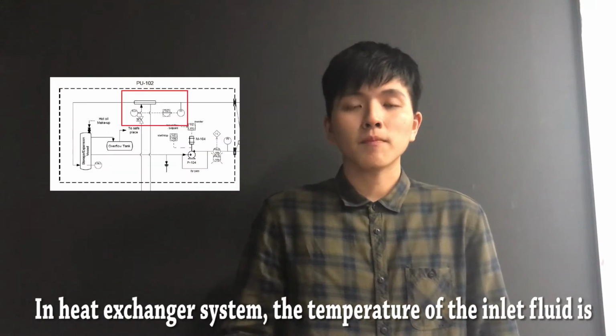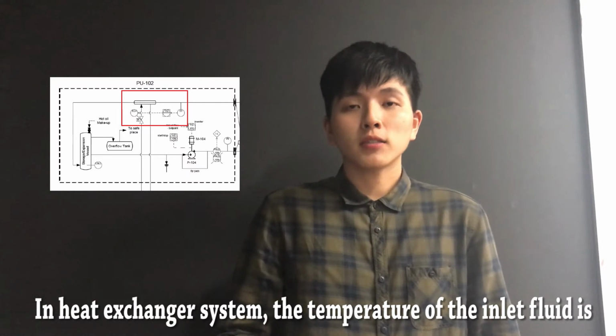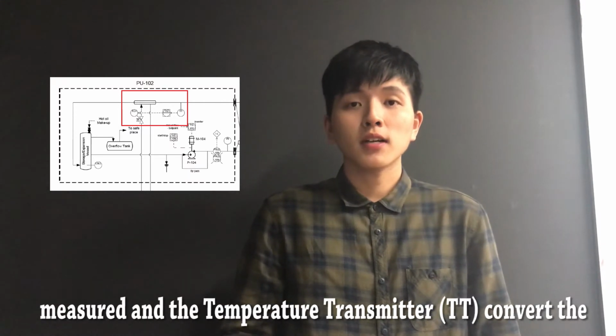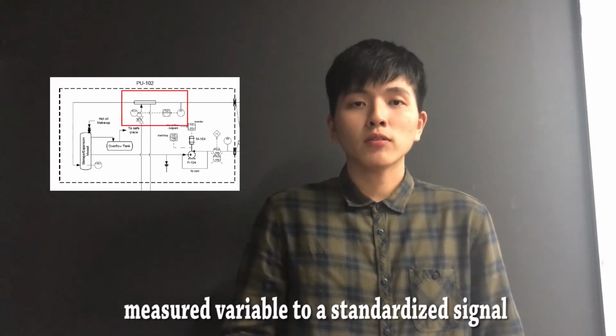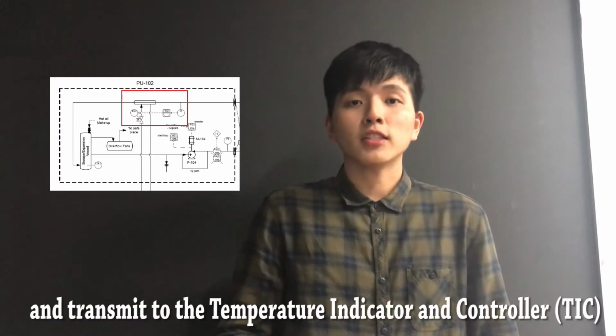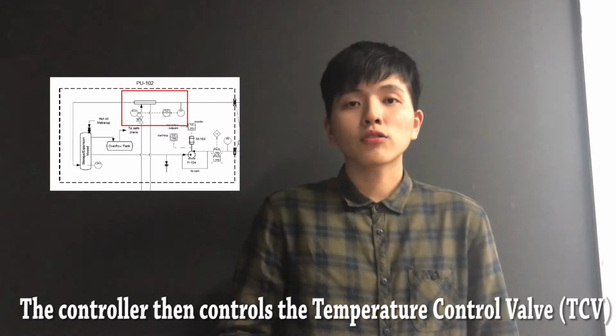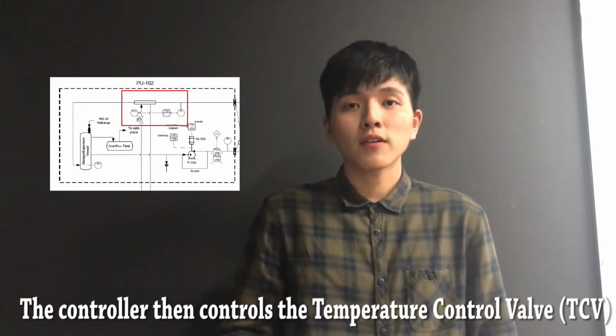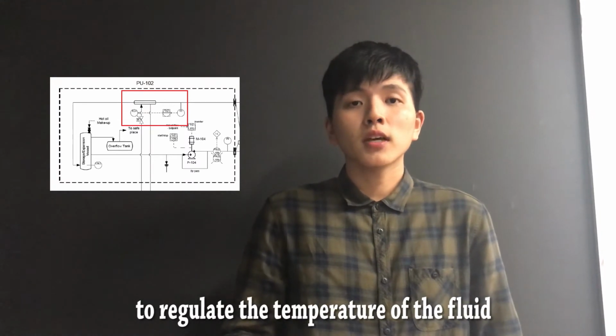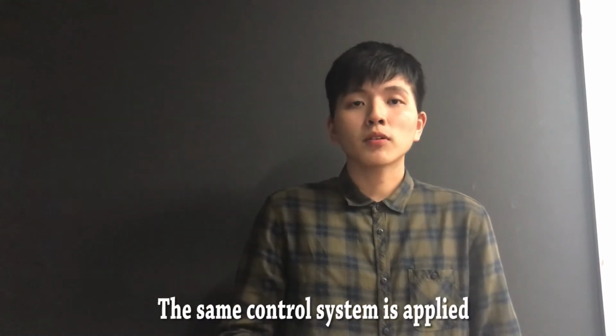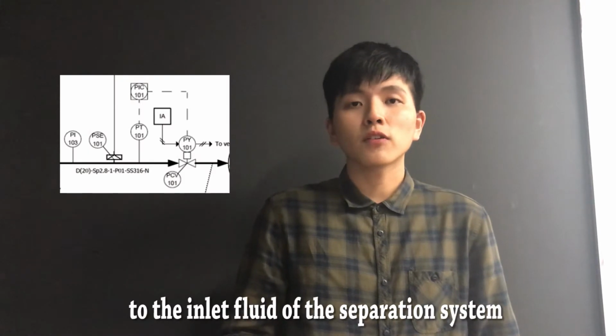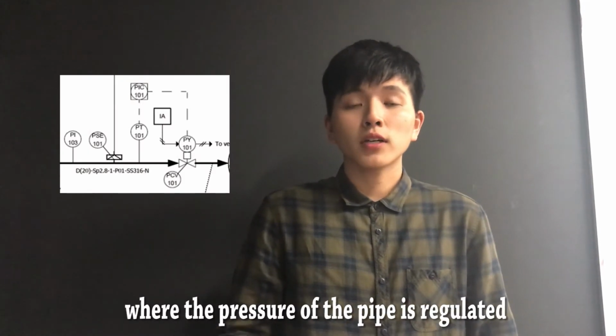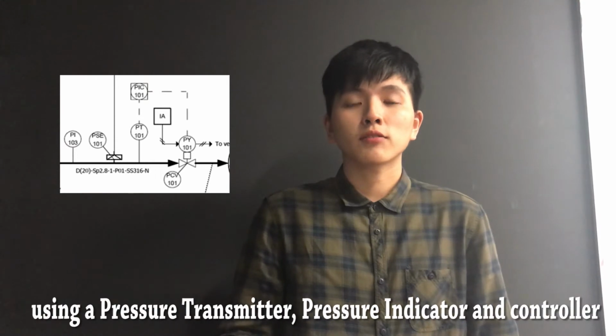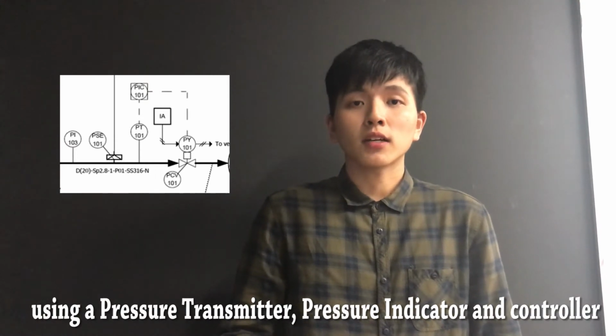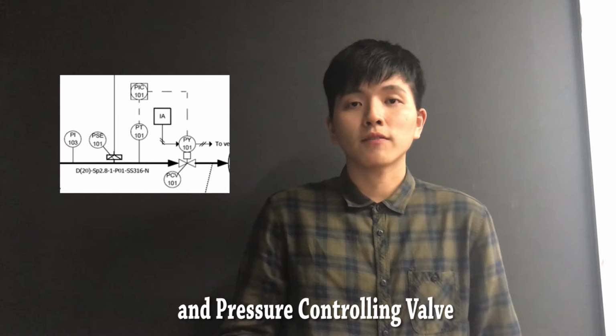In the heat exchanger system, the temperature of the inlet fluid is measured and the temperature transmitter converts the measured variable to a standardized signal and transmits it to the temperature indicator and controller. The controller then controls the temperature control valve to regulate the temperature of the fluid using cooling water. The same control system is applied to the inlet fluid of the separation system, where the pressure of the pipe is regulated using pressure transmitter, pressure indicator and controller, and pressure controlling valve.